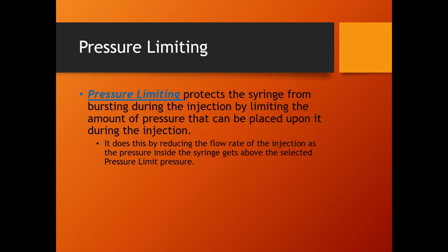So if the injector doesn't stop the injection when we hit pressure limit, what does it do to keep the syringe from over pressurizing and possibly bursting? It just slows the injection down, okay? There will also be an audible tone when the injector hits the pressure limit. There'll be a beep that lets the operators know, hey, we just hit the pressure limit on our injection. So when you hit the pressure limit, it just backs off on the flow rate, okay?